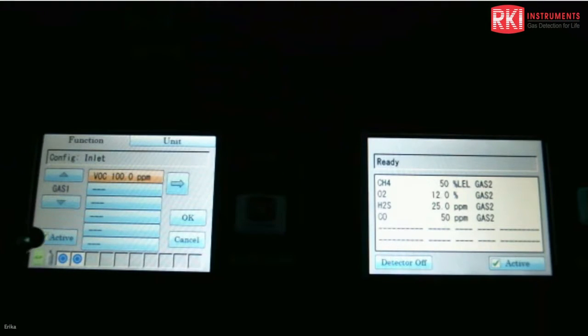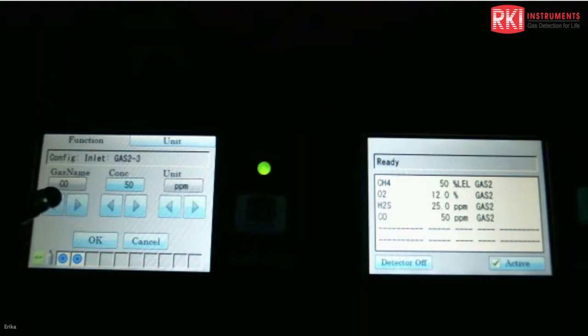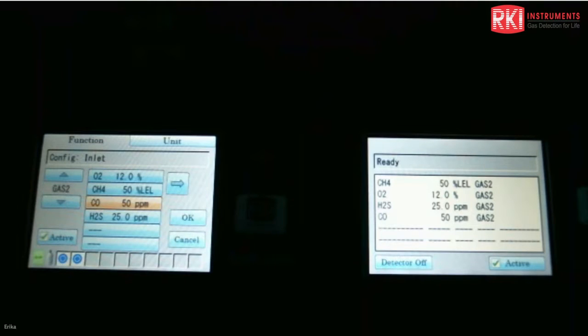So that's gas 1, and there's also an active and inactive button here. That just means gas 1 would be active. If it's inactive, it won't run that gas. So make sure that's checked. So we'll go to gas 2, which I have the standard 4 gas. Just make sure the concentrations match the cylinder, and you can change them around as well. And same with gas 3. I have HCN 10 ppm, which is what I want, and make sure everything is active on that gas port.